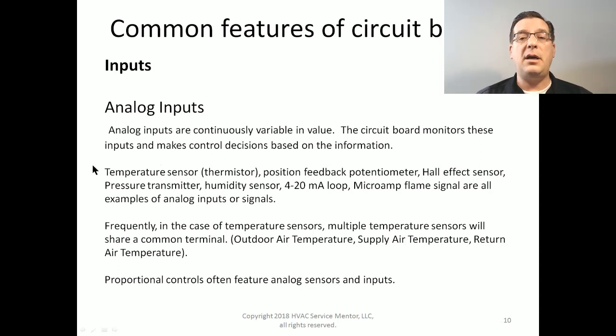Some examples of analog inputs are things like a temperature sensor, which is also known as a thermistor. Sometimes it's a thermocouple temperature sensor. A position feedback potentiometer, which is going to identify what position a movable damper or valve is in, and it's going to send that position feedback back to the main controller, and the controller is going to make decisions based on that feedback information.